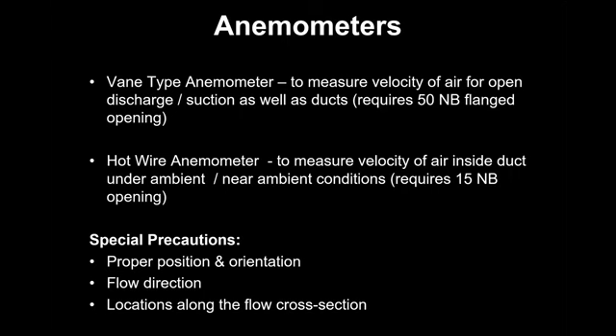So vane type anemometers and hot wire anemometers are normally used for air applications from maybe 10-15 degrees temperature to 50 degrees or 40 degrees temperature. And plastic anemometers are not suitable even for cooling towers, because they cannot take that kind of humidity, and the connection, because EMF is generated, doesn't take the humidity. So for that, there are some metallic blade anemometers available. We know at least 2 companies who are making it. That comes with a metallic blade and up to about 50-degree temperature.